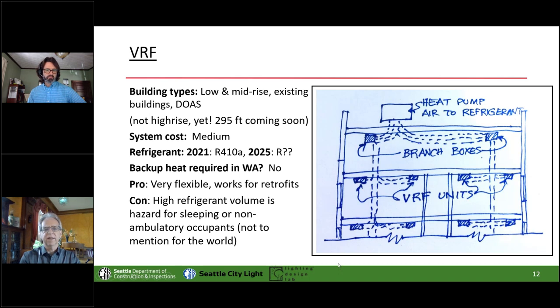You'll notice that it's been restricted up until now to what, 90-ish feet? Is that about right, Ben? It was 90 or 100. I just got the new series from a major manufacturer that can go to 135 from the bottom or 150 from the high, if the condenser sits on the roof. So that's rapidly improving. That was news to me and kind of exciting. And that 295 is sort of the overall developed length, is that right? Yeah, that's down and back. It's the total loop length.